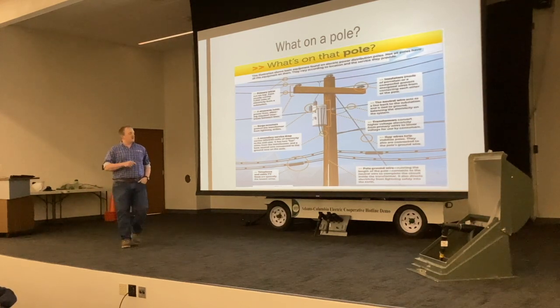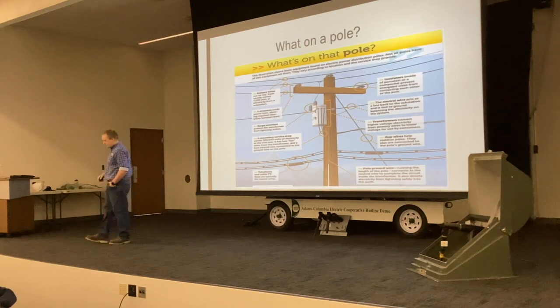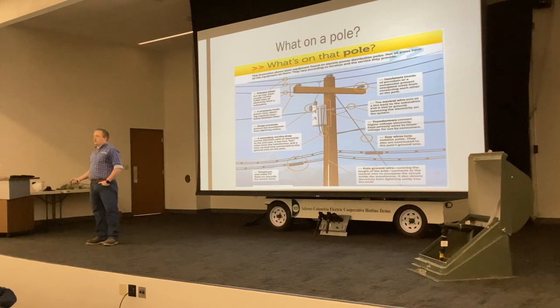So remember this, we're taking 7200 and we're going to change it to 120, 240. Now if I told you we pump 120, 240 in, what do you think is going to pop out the other side? Say it was wired exactly the same. We just reversed it. 7200. It's exactly what it does. That is an example of backfeed.